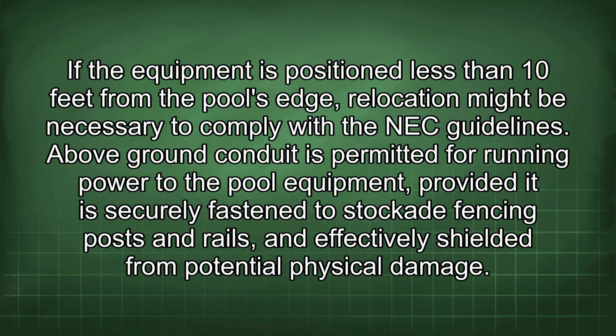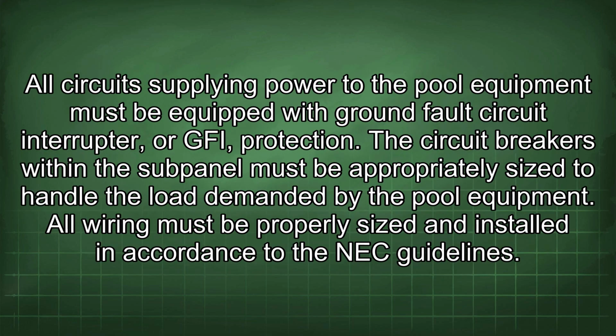the NEC guidelines. Above-ground conduit is permitted for running power to the pool equipment, provided it is securely fastened to stockade fencing posts and rails and effectively shielded from potential physical damage. All circuits supplying power to the pool equipment must be equipped with ground fault circuit interrupter, or GFI, protection. The circuit breakers within the subpanel must be appropriately sized to handle the load demanded by the pool equipment. All wiring must be properly sized and installed in accordance with the NEC guidelines.